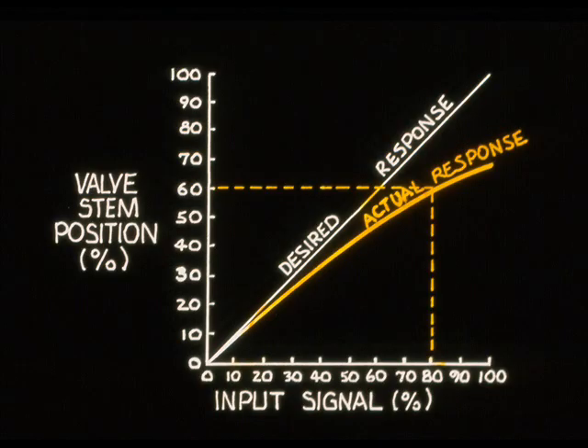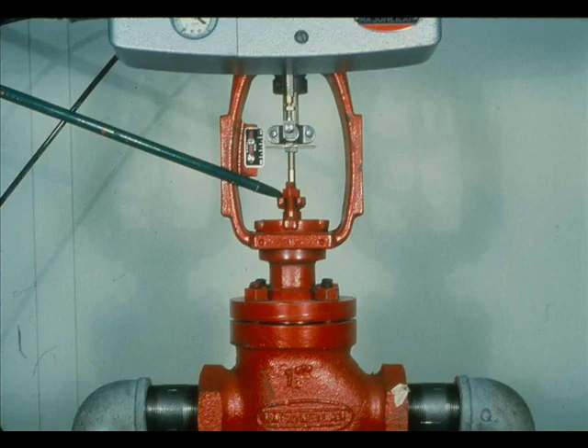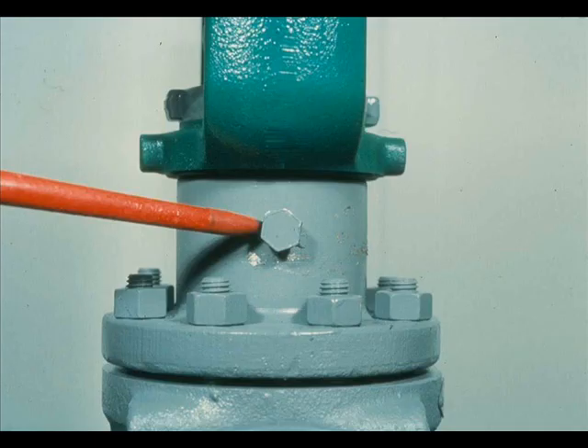Many factors prevent the control valve stem from assuming the correct position. For instance, high pressure drop across a valve may occur on 80% input to produce only 60% valve stem travel. Other factors which can cause non-linear input versus valve stem position are tight packing or no packing lubrication when it is required.